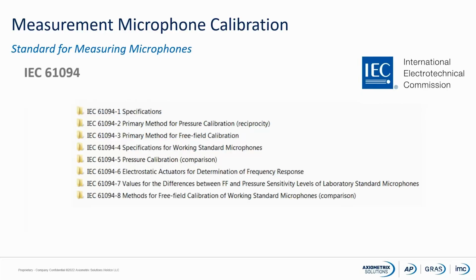Parts 2 and 3 describe how to do calibration of the laboratory reference microphones: pressure calibration and free field calibration. IEC 61094-4 is the specification for a working standard microphone. It's actually the microphone most of you have on your table. It's the microphone most of you are using every day. The specifications for this type of microphone are described in this part of the measurement microphone standard.